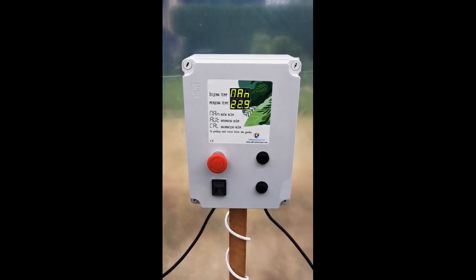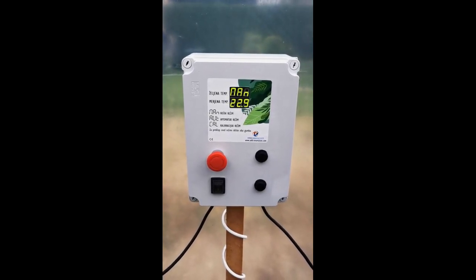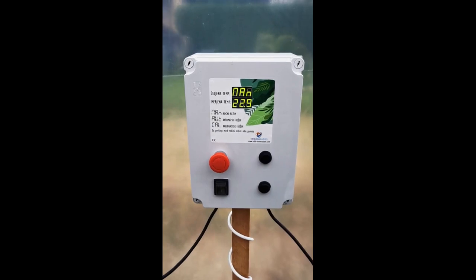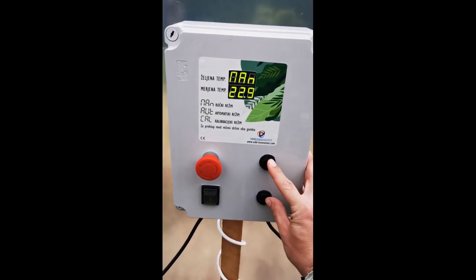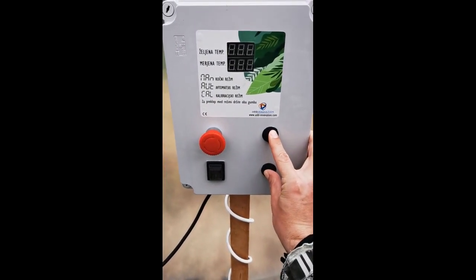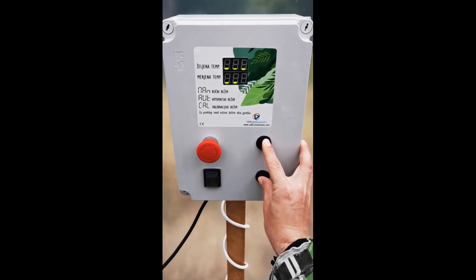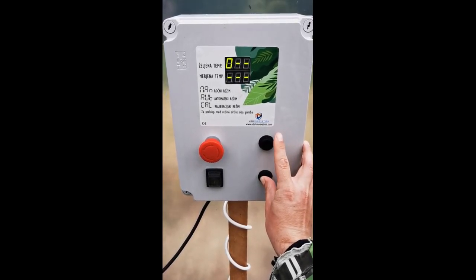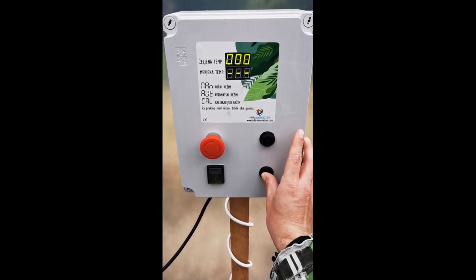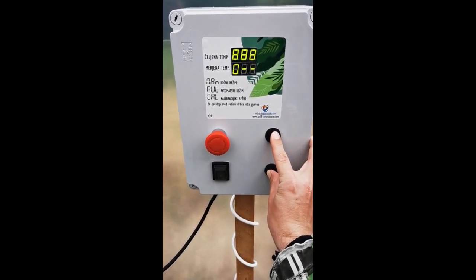Calibration is probably the easiest part of the whole assembly. To get to the calibration mode on the box, we must first switch to the manual mode. Then hold both buttons until 6 lines appear on the screen. Let's just release the top button. Zeros will start to appear on the screen. When 3 8s appear, press the top button back.